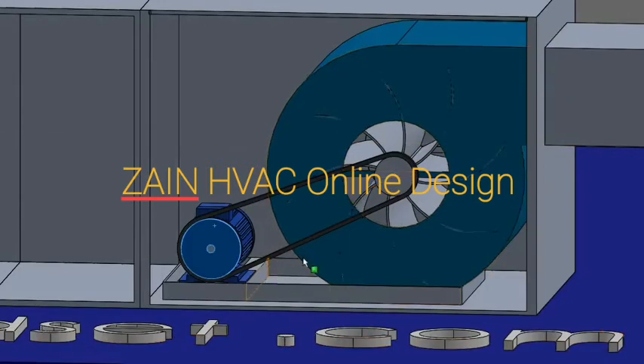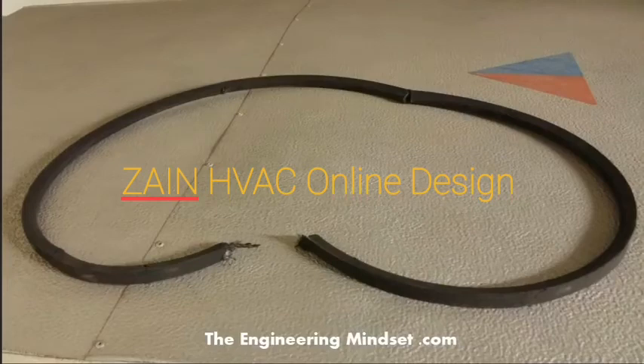Now I mentioned the belt drive there. These belts also need to be replaced periodically. They will break, and they will wear down. In fact, I've got an example here. This is a broken V-belt used on one of the AHUs, and you can see there it's just completely snapped, and this has had to be replaced.